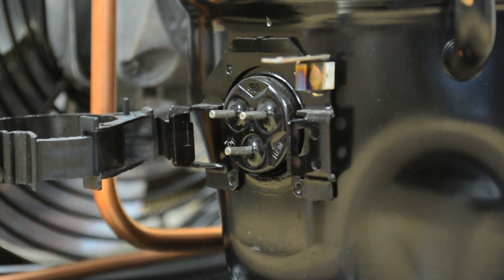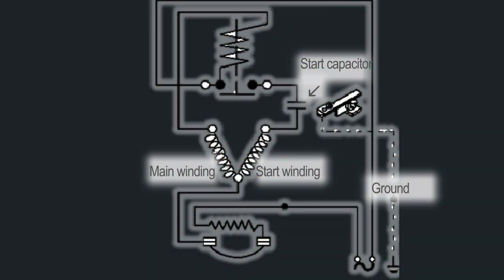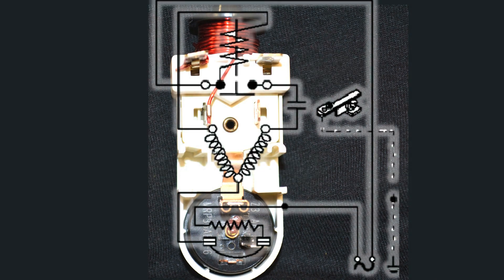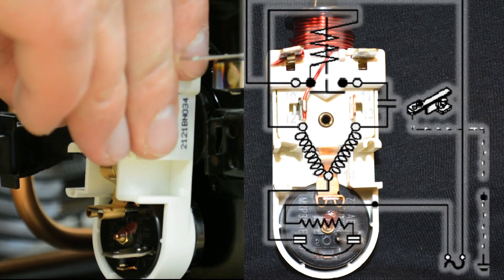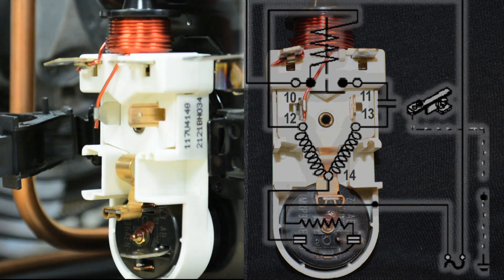With the pins properly identified we will be able to understand the wiring diagram. A current relay such as this one has normally open contacts that close due to the inrush of current when the compressor starts. Once the initial inrush of current passes, the current relay contacts reopen to their normal position, which de-energizes the start winding and removes the start capacitor from the circuit.